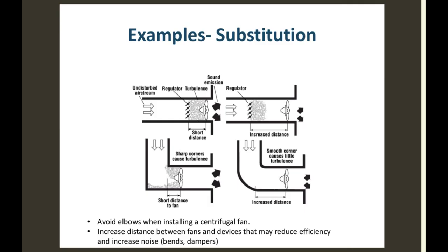So if the room gets warm and we need more cold air, they open a little more, but not wide open, right? So it could be the controls are bad, could be the dampers are jammed, could be a number of reasons, but the reason for the noise was the velocity was too great. Same thing with an industrial ventilation system. The velocity has to be high enough that you capture the contaminant, keep it suspended in the air so you can get it out of the building.